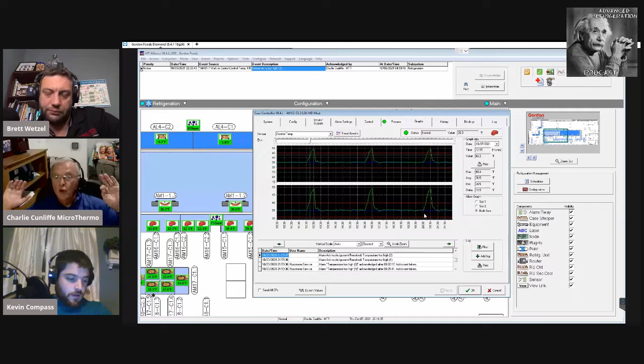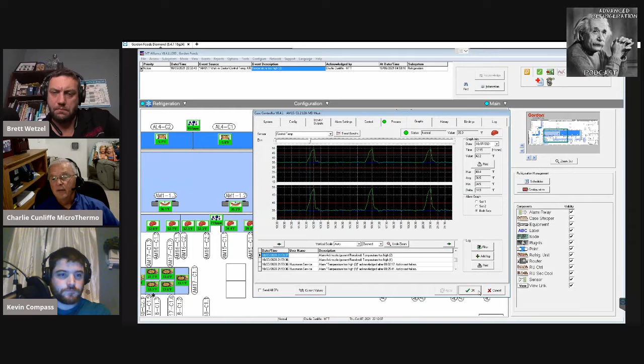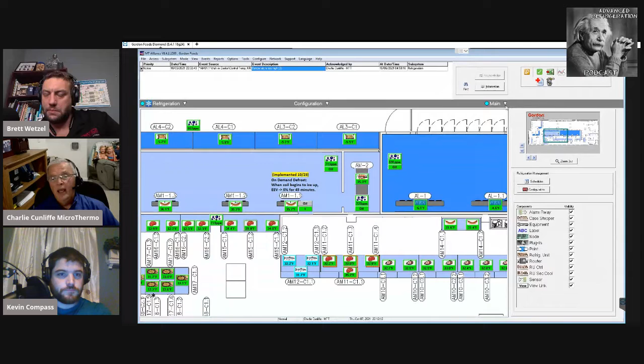And with CO2, I'm going to say 99% of the stores I've done, it's all been temperature control with superheat limit. And I mean, these are beautiful graphs. That's exactly what you want to see. This is getting your money's worth out of electronic controls. If you pull up a graph and it's haywire and it looks like a mountain chain with a bunch of ridiculous spikes all over the place, you've got to go in, and just like Kevin said, there's off the shelf.